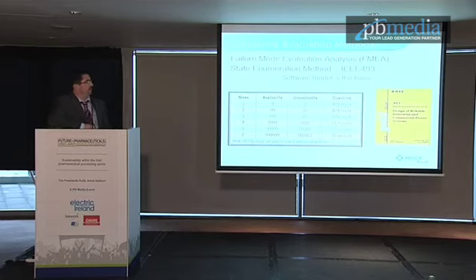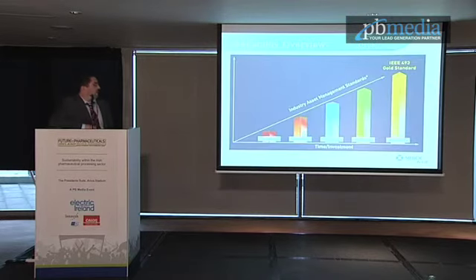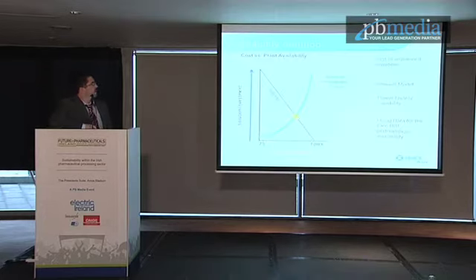Reliability evaluation here from the IEEE standard is one of the best methods of doing it. So where the Rathdrum facility got itself was from a firefighting situation here on the right hand side across to between optimization and reliability. This was done without any increase in maintenance headcount, and just by restructuring the way we were doing our business. The reliability solution, so your solution investment should be rated against your plant availability requirement and the cost of unplanned downtime and the power quality capability on your system.